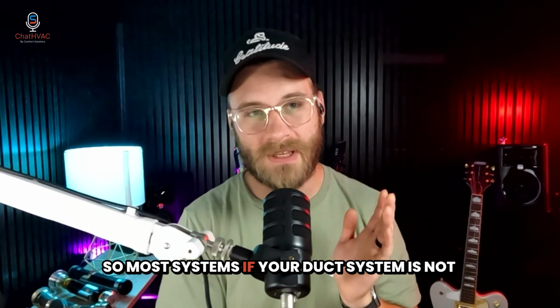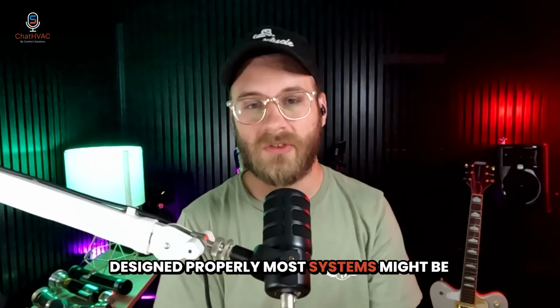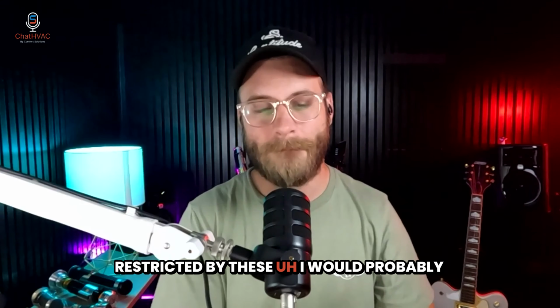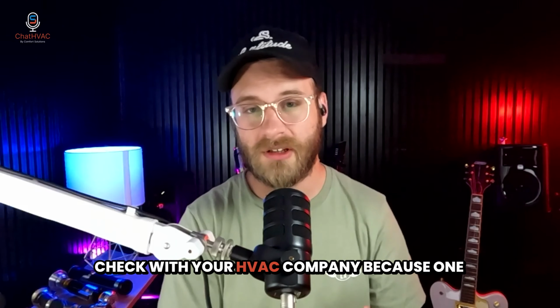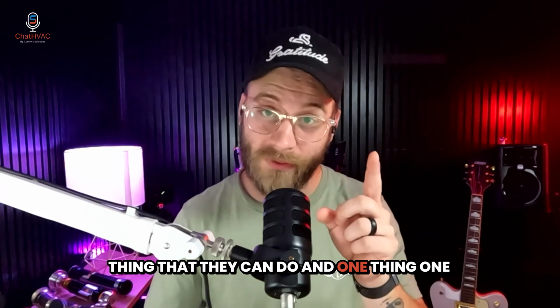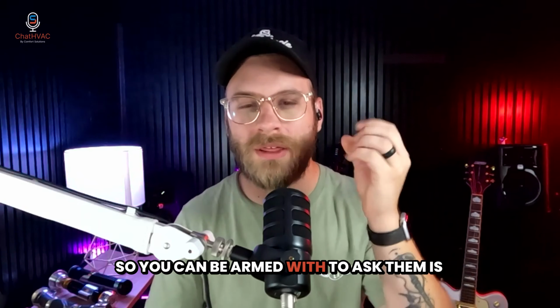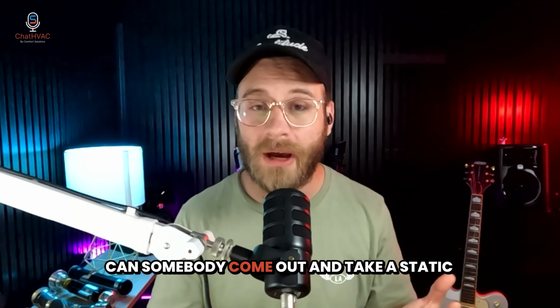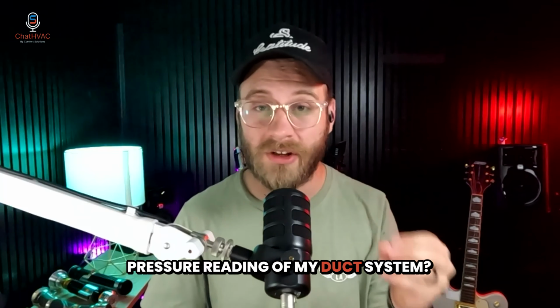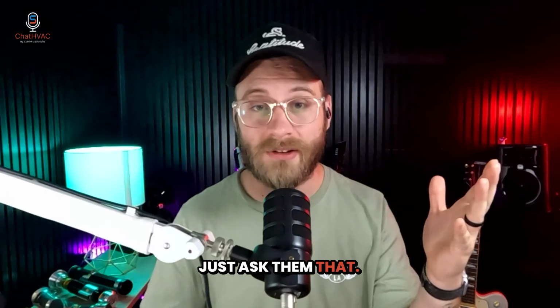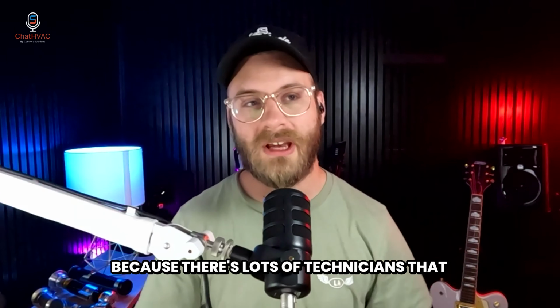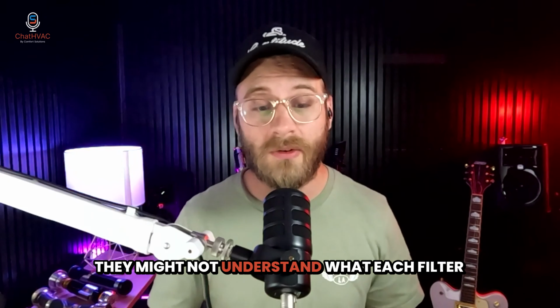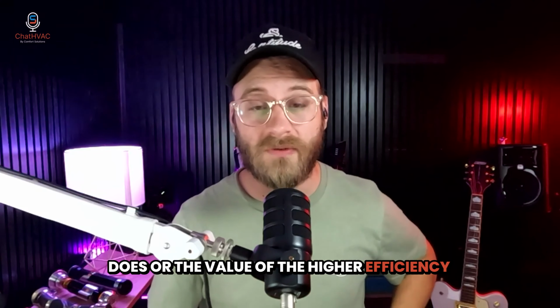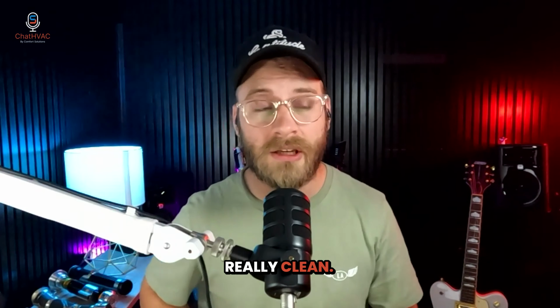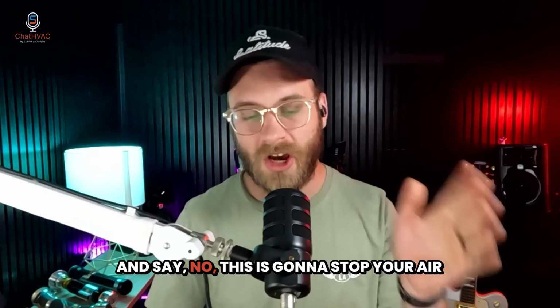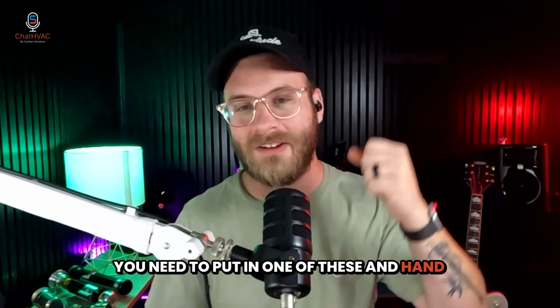So most systems, if your duct system is not designed properly, might be restricted by these. I would check with your HVAC company, and one piece of information to be armed with when you ask them is, can somebody come take a static pressure reading of my duct system? Just ask them that, because there are lots of technicians who might not understand what each filter does, or the value of higher efficiency filters like your MERV 16 to keep your air really clean. They'll just look at a MERV 16 filter and say, no, this is going to stop your air up, you need one of these, and hand you a fiberglass filter.